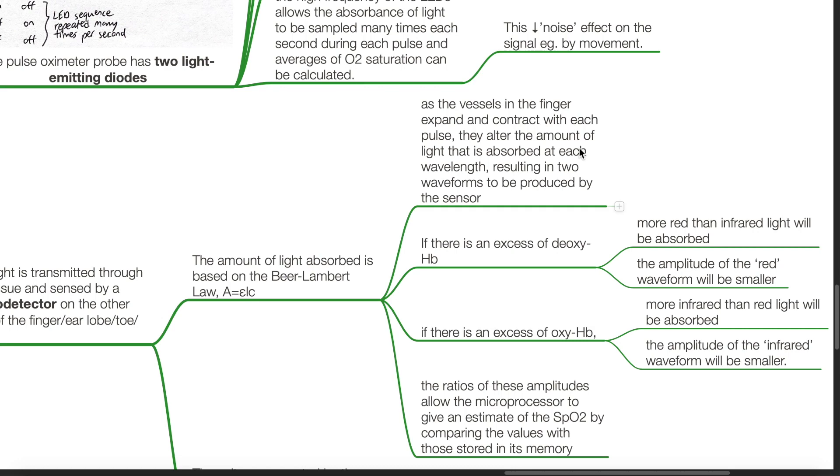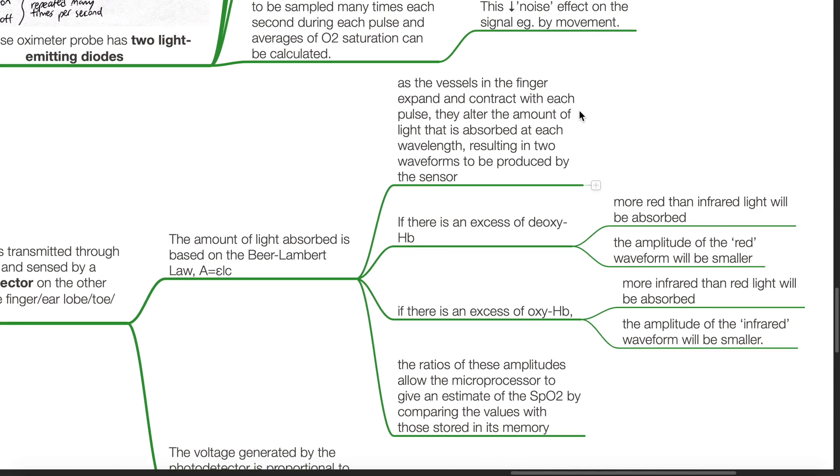As the vessels in the finger expand and contract with each pulse, they alter the amount of light that is absorbed at each wavelength, resulting in two waveforms produced by the sensor. If there is an excess of deoxyhemoglobin, more red than infrared light will be absorbed and the amplitude of the red waveform will be smaller. If there is an excess of oxyhemoglobin, more infrared than red light will be absorbed and the amplitude of the infrared waveform will be smaller.